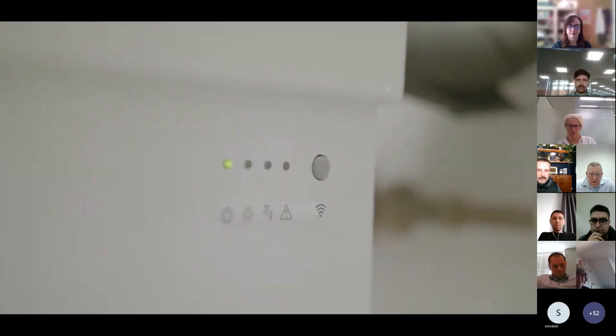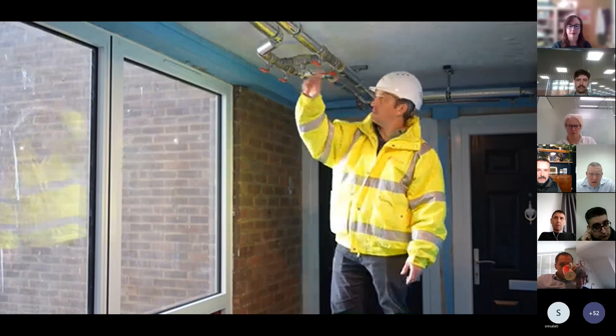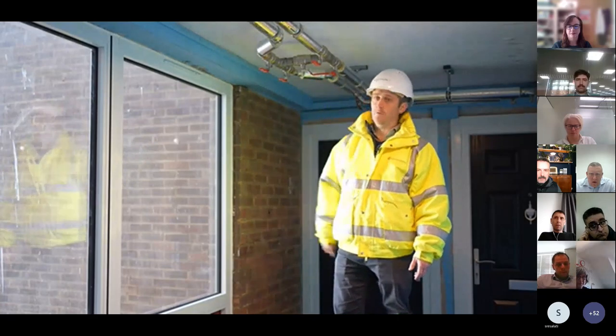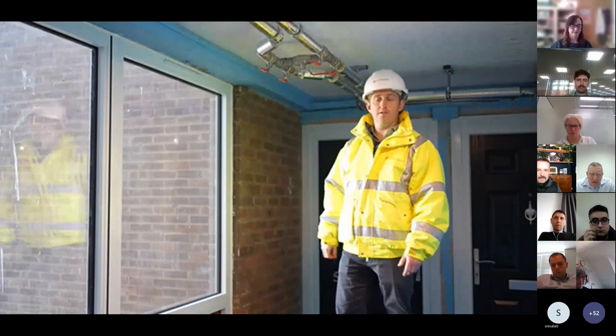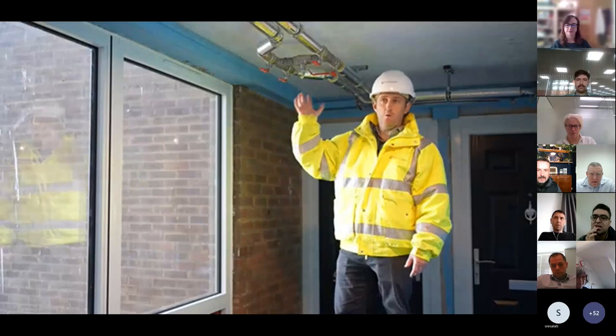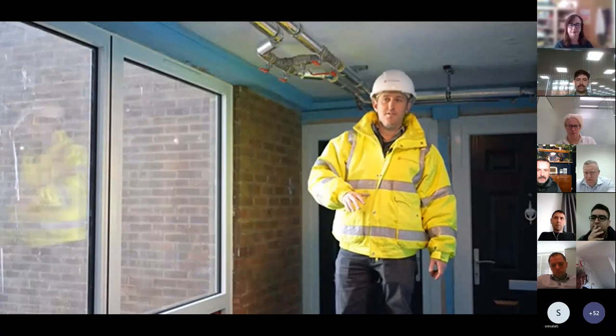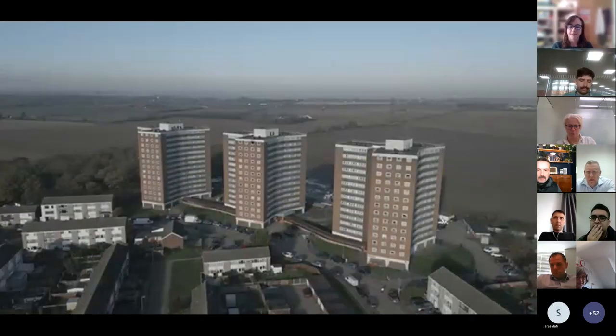Once that's done and we know the heat pump's ready to set to run and commission, because we've got flow, we'll basically open these four valves, close the one in the middle, and that's the system ready to run and circulate flow from the heat pump all the way down through the laterals, risers, and then into the boreholes.